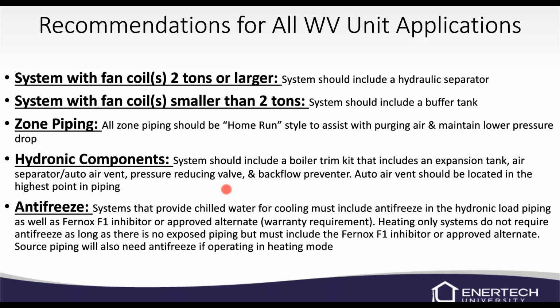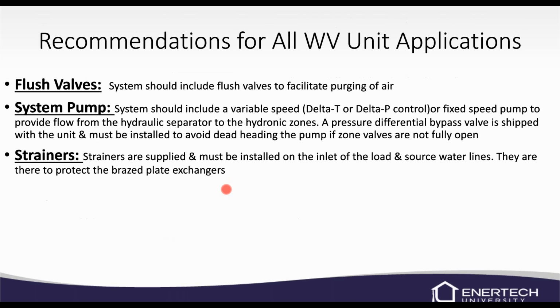Heating only systems do not require antifreeze as long as there's no exposed piping, but you must include the inhibitor. And source piping will need antifreeze whenever you're operating in heating mode. So make sure it's got inhibitors in your source piping as well. Flush valves. Systems should include flush valves to facilitate the purging of the air. If you're going to install a buffer tank or a hydraulic separator, make sure that you're installing flush blocks on the secondary side of the buffer tank or hydraulic separator so that you can flush the load zones.